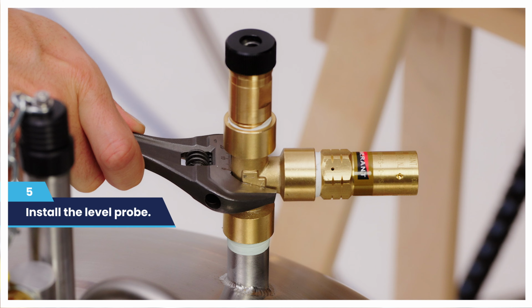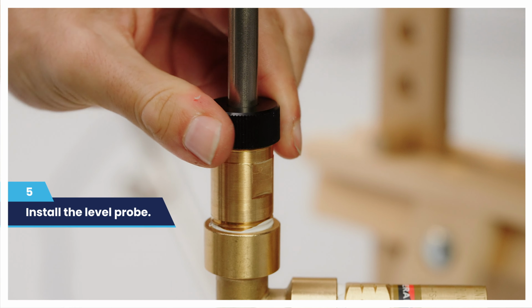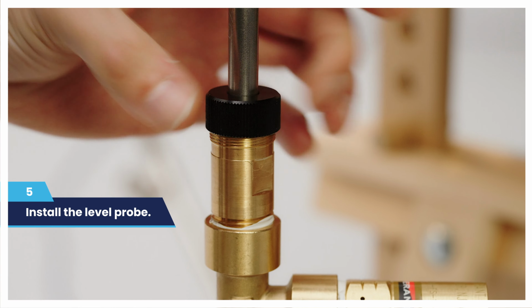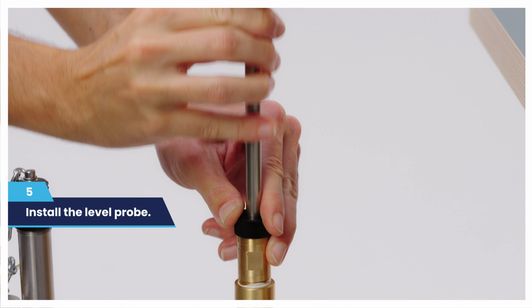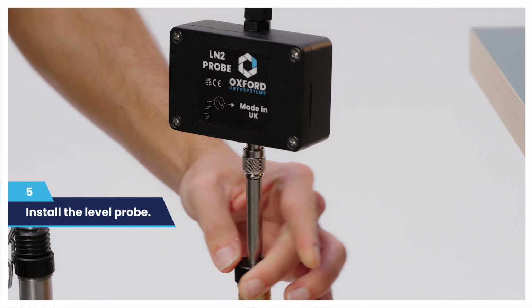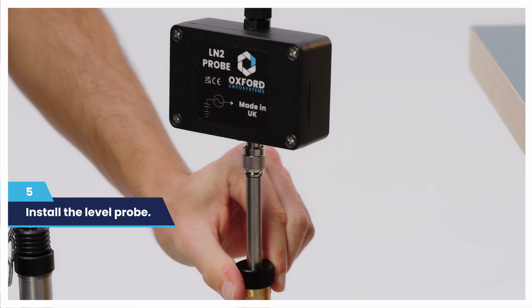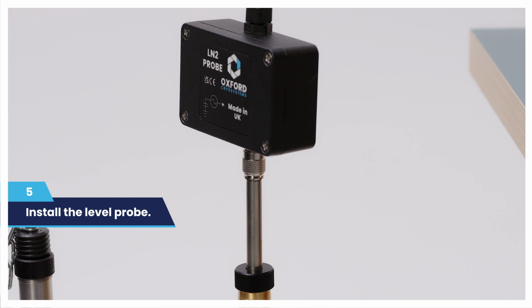Screw on the probe adapter, loosen the cap and insert the level probe. Do this slowly so as not to damage the probe. Once you can feel the probe is touching the bottom of the dewar, let go and retighten the cap.